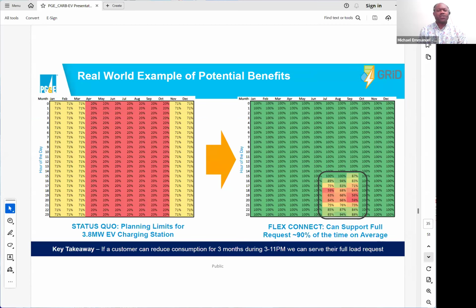This slide shows a real-world example of a site that is capacity constrained. On the left-hand side is what you'd get from your load limit letter. This site is capacity constrained to operate at 20% of the capacity request. For this developer, the request is about 3.8 megawatts, but the planning limit says you can only have 20%, about 0.7 megawatt of what you're asking for. For an existing customer, that means between April and October they'll have to operate at 20% of what's requested.